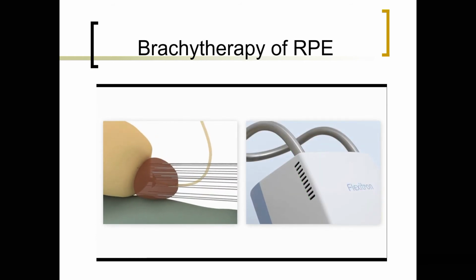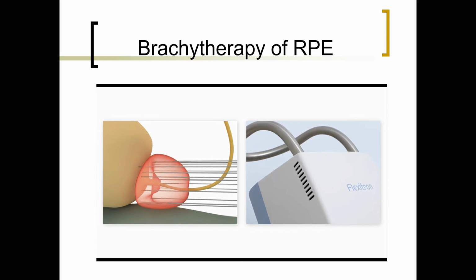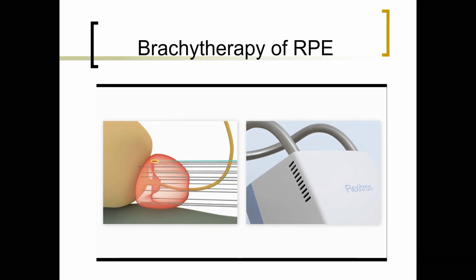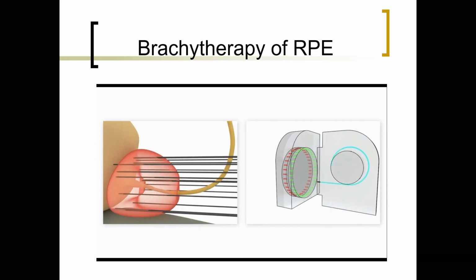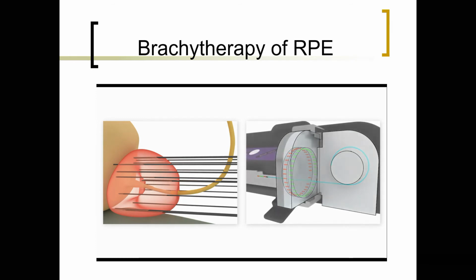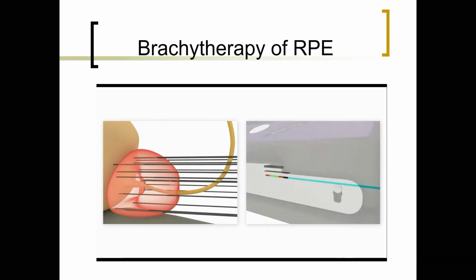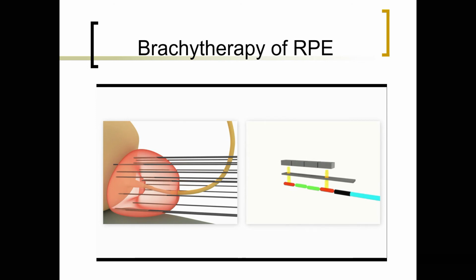For delivery of HDR prostate brachytherapy, the needles are connected to the afterloader. This device transports a radioactive source into the needles to the planned dwell locations and radiates the target area. For prostate brachytherapy with seeds, the seed selectron transports a seed train into each of the needles. Plan optimization based on the actual situation can be done after each seed train insertion.